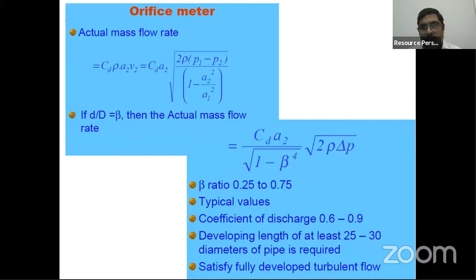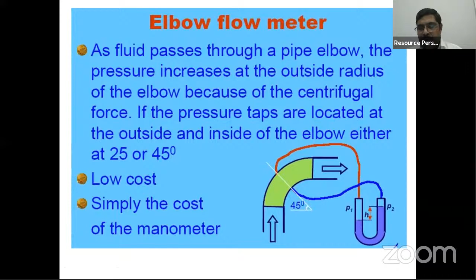Okay, fine. The elbow type flow meter is also used in the refinery industry. When the flow goes through an elbow, because of the centrifugal force, the pressure experienced is maximum at the outer side compared to the inner periphery. So we take a pressure tapping between the inner bend and the outer bend. Between these two sections you get the pressure drop, and from the pressure drop you can get the flow rate.